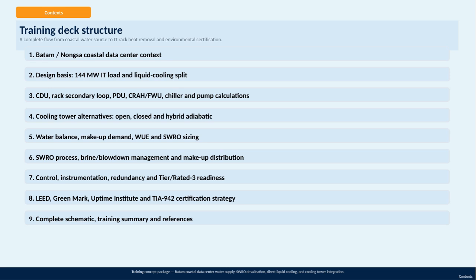Following that, we dive into detailed calculations involving the CDU, rack secondary loops, power distribution units, CRAH/FWU units, chillers, and pumps. Then, we explore different cooling tower alternatives, including open, closed, and hybrid adiabatic towers. The next section covers the water balance, makeup water demand, water usage efficiency, and sizing of the SWRO system. We then explain the SWRO process itself, along with brine and blowdown management and distribution of makeup water.